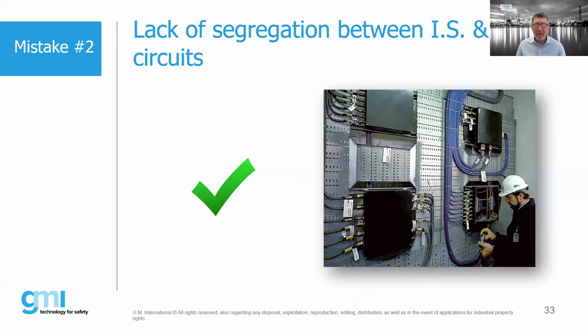But is it not true that if the partition is metal between the IS and non-IS, it has to be grounded? Yes, typically it would have to be grounded. Somebody's asking if we can reduce this distance without applicable for wire duct.